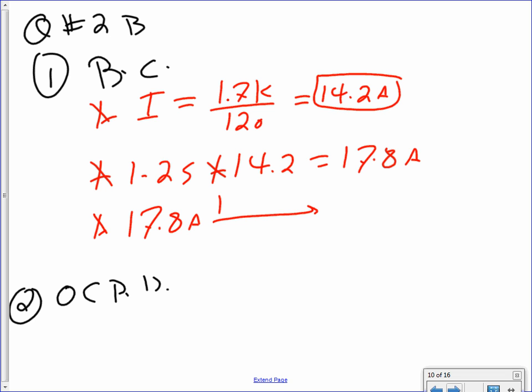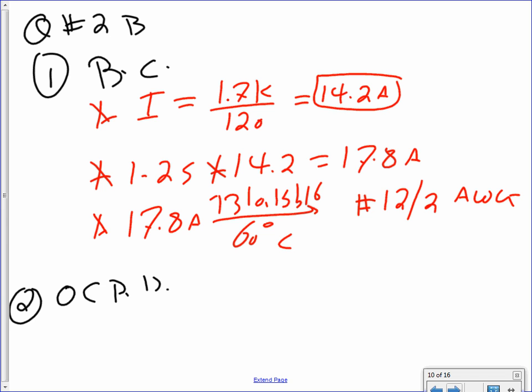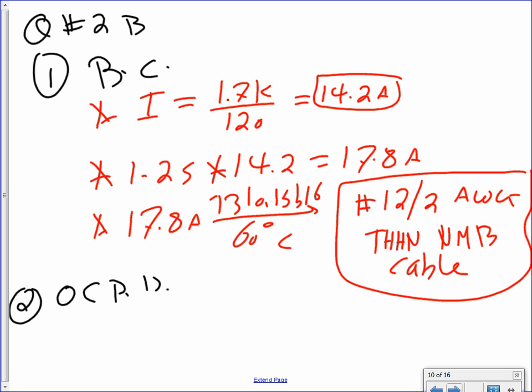Take this to Table 310.15(B)(16) under the 60 degree Celsius column. The conductor is going to be number 12-2 AWG, and insulation THHN, NM cable. So it's a 12-2 cable, NM cable. The conductors in an NM cable are THHN. If you don't believe me, go to the article that talks about NM cable. It tells you that they are insulated at 90 degrees Celsius, which is THHN.